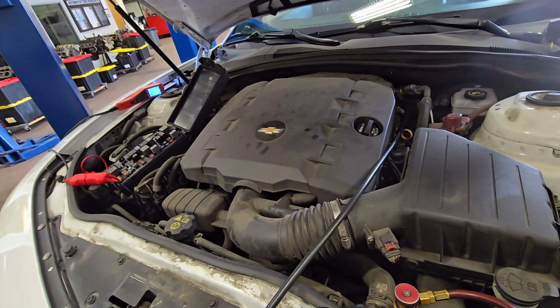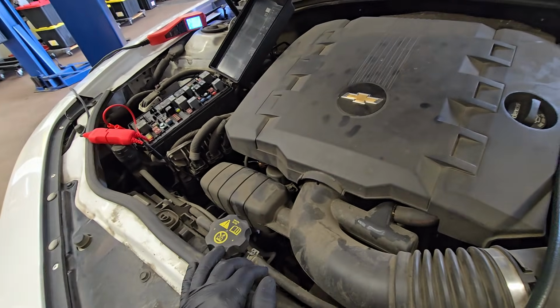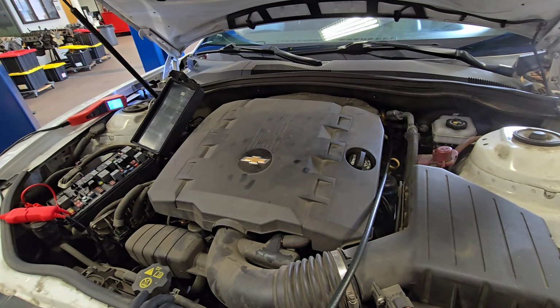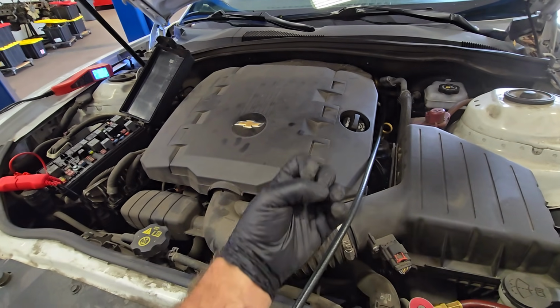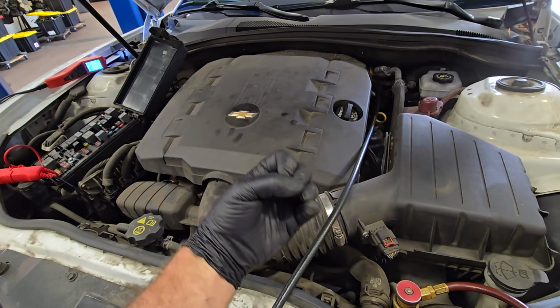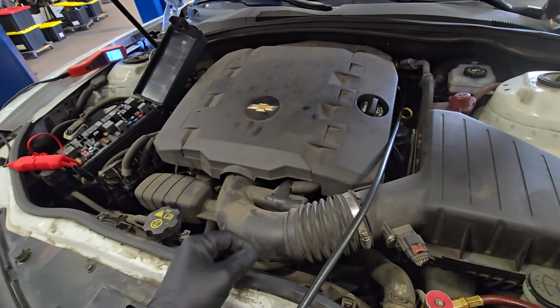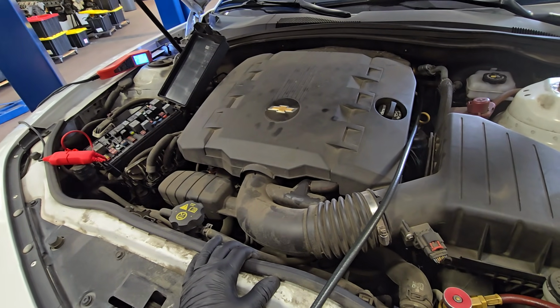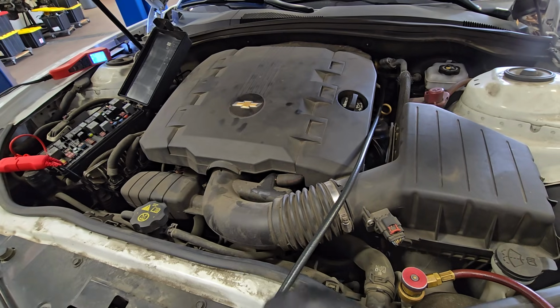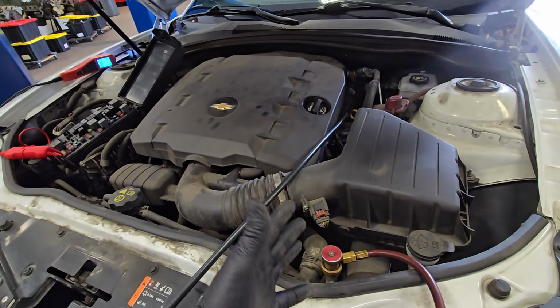When the system's low on refrigerant, the low pressure cycling switch or the refrigerant pressure sensor will see that it's low, and in an effort to protect itself, it will not command the compressor on. So I could do a little more troubleshooting, but I kind of don't need to.